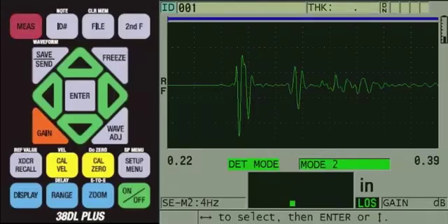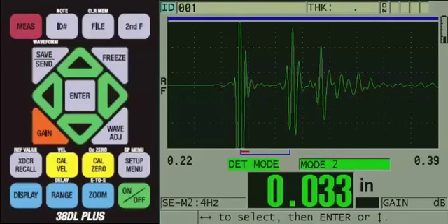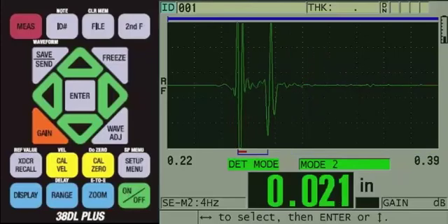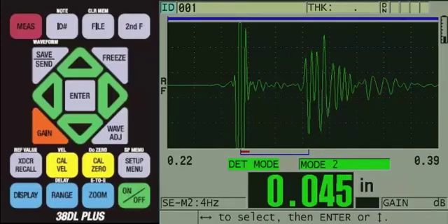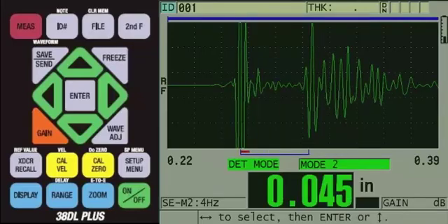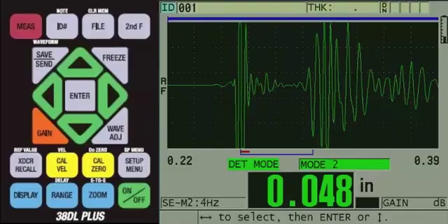As discussed earlier, you'll notice variations in thickness and echo quality when measuring from point to point on the same sample. In many cases, the same gauge that is used for Gelcoat measurement can also be used to measure total wall thickness. To measure the total thickness of the Gelcoat and fiberglass sample, we would recommend viewing the fiberglass and composite application guide, where we use low-frequency transducers to make these measurements.